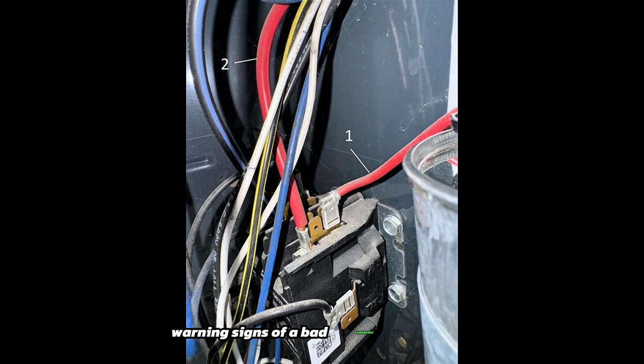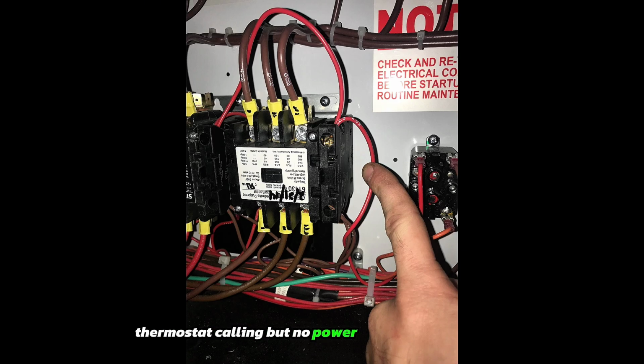Warning signs of a bad contactor or relay: buzzing noise but no operation. Motor tries to start but cuts off. Burned, blackened, or stuck contacts. Thermostat calling but no power reaching the motor. Melted terminals or insulation. If you see any of these, test the coil, replace the part, and restore operation.